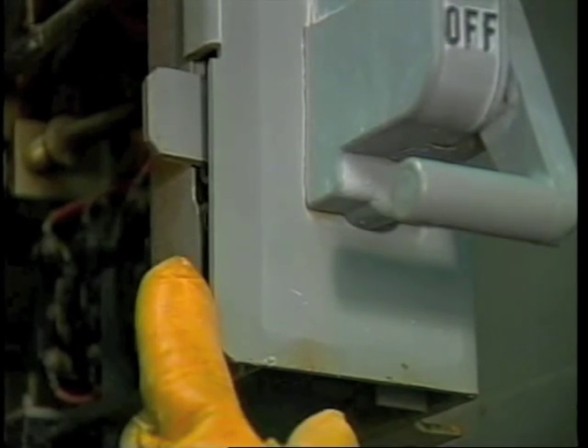Be sure that all mechanical interlocks have functioned properly. These devices are designed to prevent access to the motor control center unless the load side is de-energized first. Identify all electrical interlocks. Electrical interlocks are designed to de-energize the control power if access is attempted without first isolating the motor load.